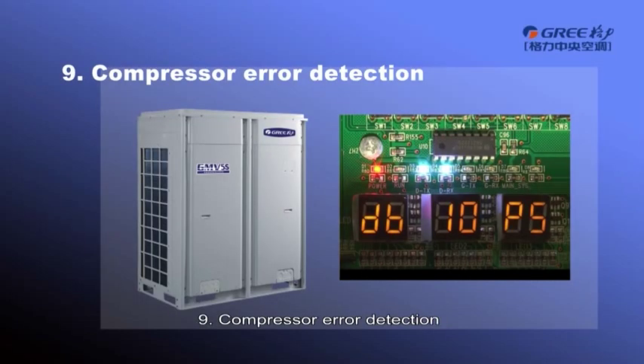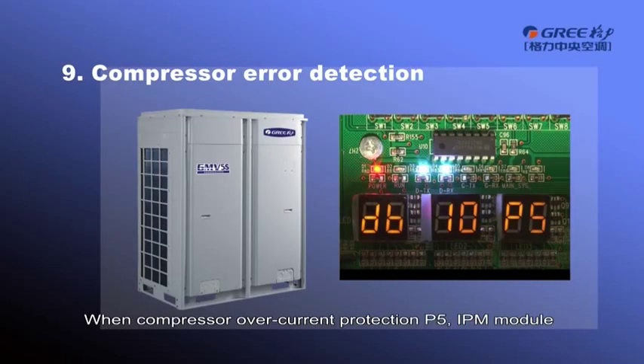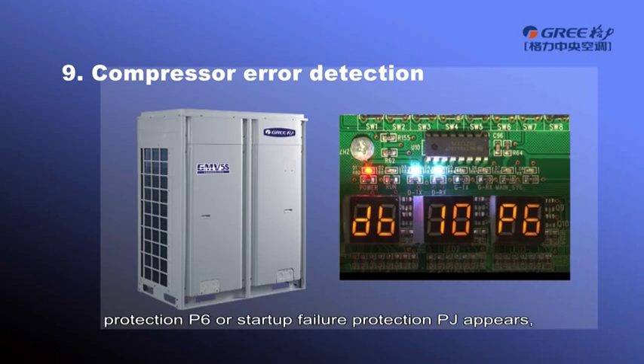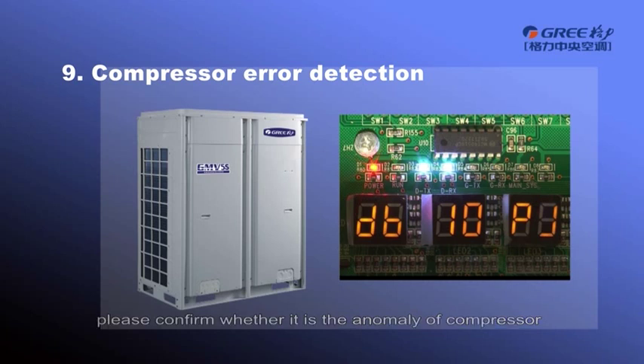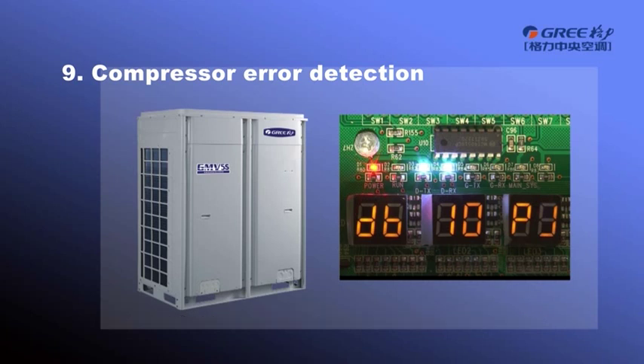Compressor error detection. When the compressor over current protection P5, IPM module protection P6, or startup failure protection PJ appears, please confirm whether it is an anomaly of the compressor or the anomaly of the IPM module. The confirmation methods are as follows.